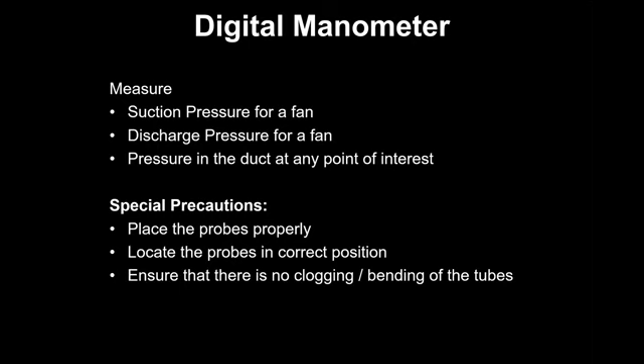Then it is also used to do pressure mapping, because many times it becomes important to map the pressure in the duct, along the duct, especially if the ducts are long. Or say there are different equipment, like you have boiler, economizer, air preheater, then there is an ESP and all that. So there we want to find out what is the pressure drop in the individual equipment and what is the pressure drop in the duct.